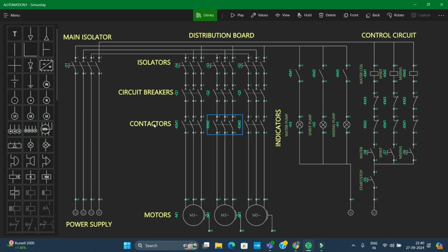These are the interlockings from these different contactors here. I'm going to explain: when I'm simulating, if one pump is on, one of its contactors over here is going to provide an interlocking here, and it's going to open up. So when it opens up, that means even if I turn on another pump, it is not going to turn on, because I only want one pump running at a time.